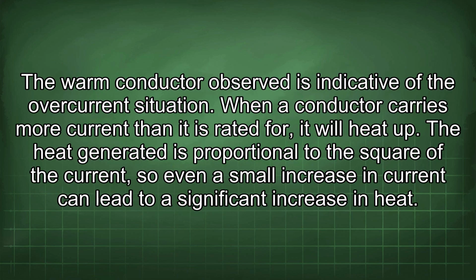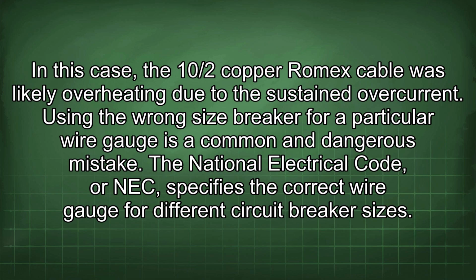The warm conductor observed is indicative of the overcurrent situation. When a conductor carries more current than it is rated for, it will heat up. The heat generated is proportional to the square of the current, so even a small increase in current can lead to a significant increase in heat. In this case, the 10/2 copper Romex cable was likely overheating due to the sustained overcurrent. Using the wrong size breaker for a particular wire gauge is a common and dangerous mistake.